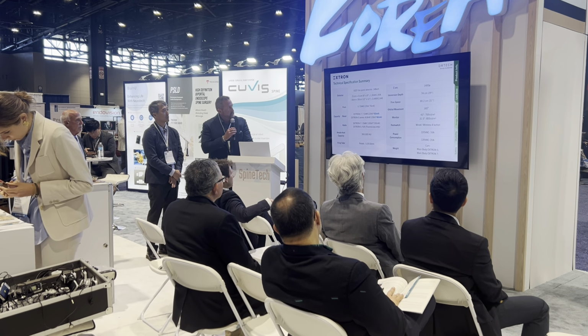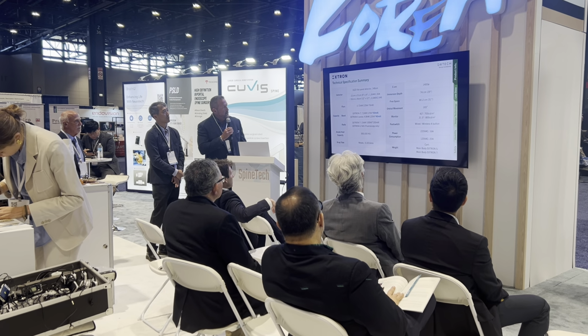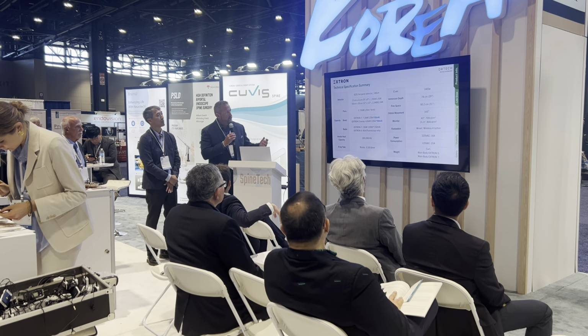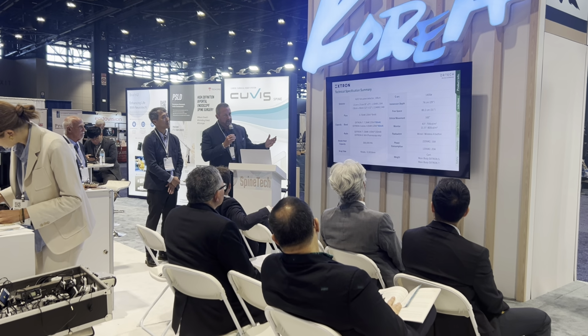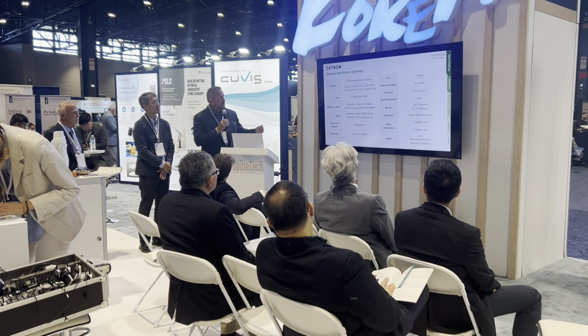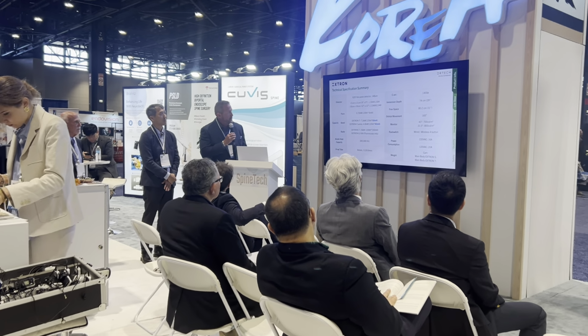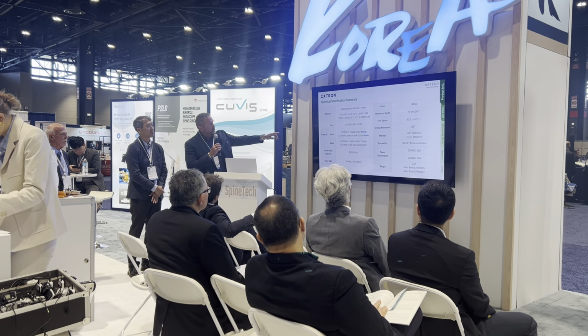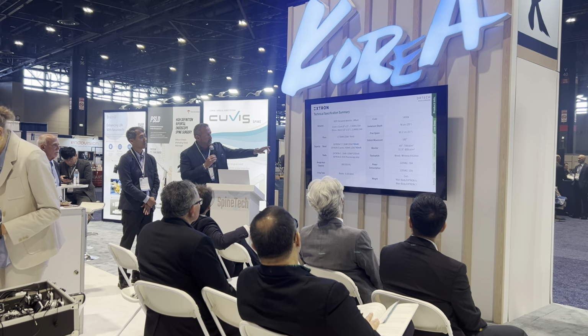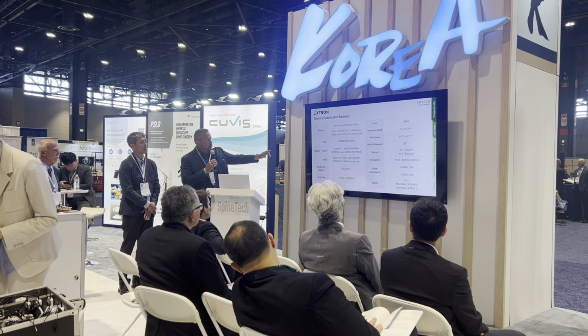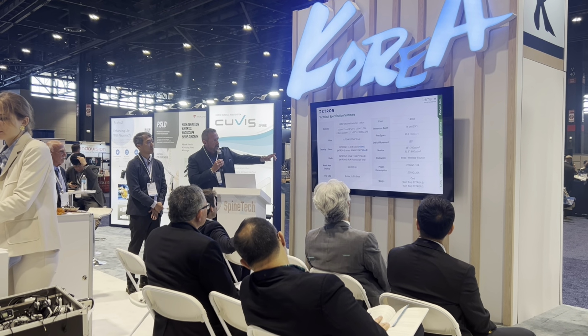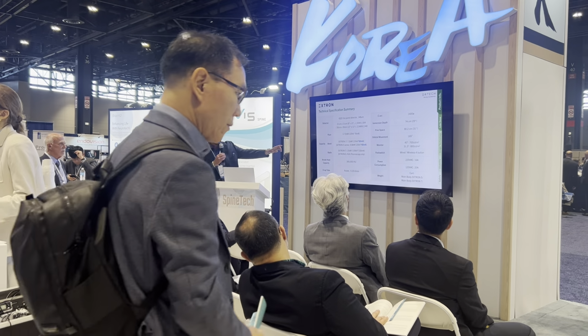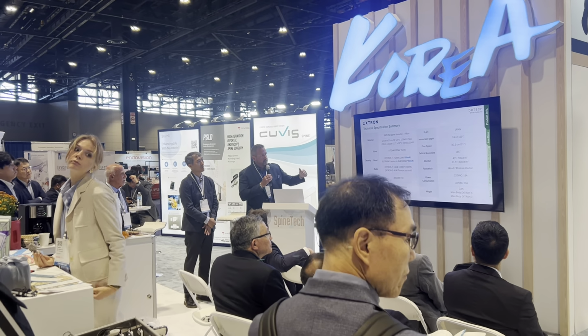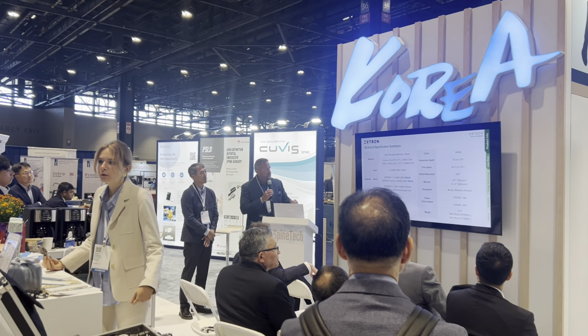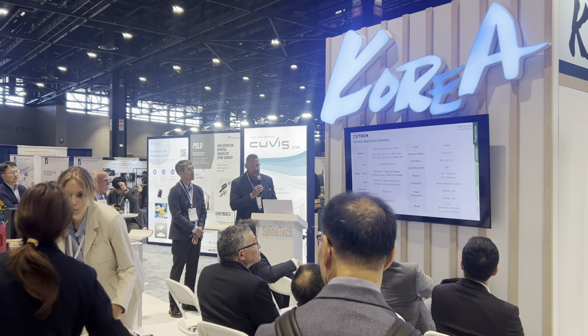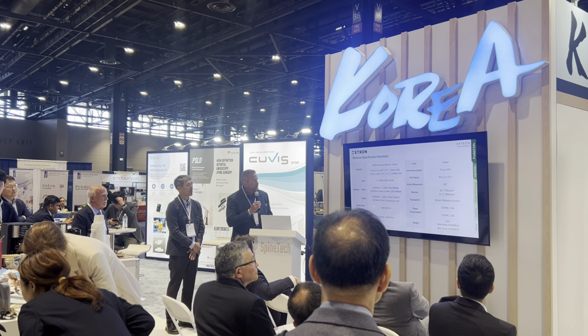We'll talk a little bit about the detector again. It comes in a 30 by 30. If you're in orthopedics doing hip replacement, or if you're doing vascular surgery, you want the bigger detector. For pain management and spine, a 21 by 21 is sufficient. You can go all the way to 120 kV at 6 mA, or in boost mode, you can go to 120 kV at 40 mA. They do have a model called the EXTRON 7 if you want to do a rad shot. If you want to do a pre-surgery or post-surgery x-ray, you can go with the EXTRON 7. You'll have that capability to do a rad shot.